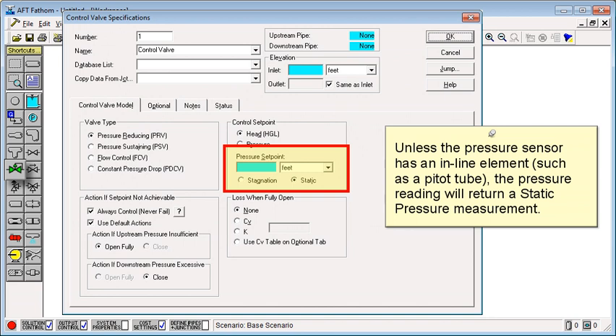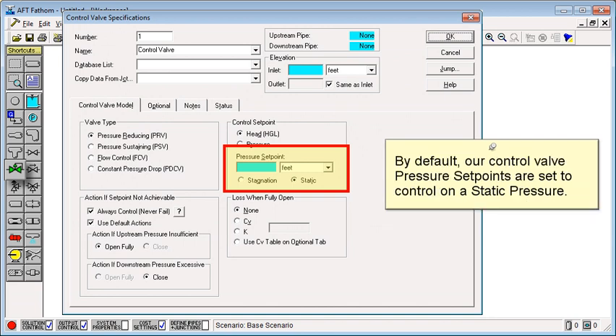Unless the pressure sensor has an inline element, such as a pitot tube, the pressure reading will return a static pressure measurement. By default, our control valve pressure set points are set to control on a static pressure.